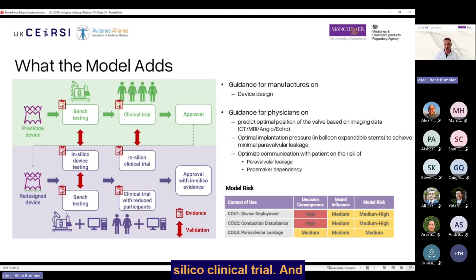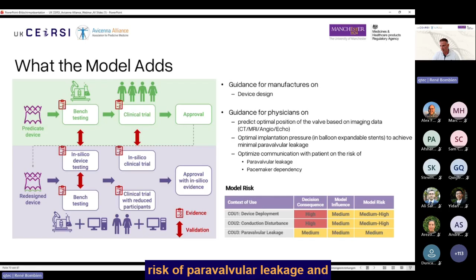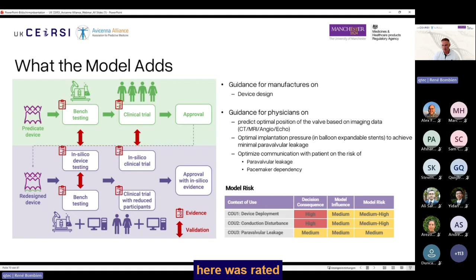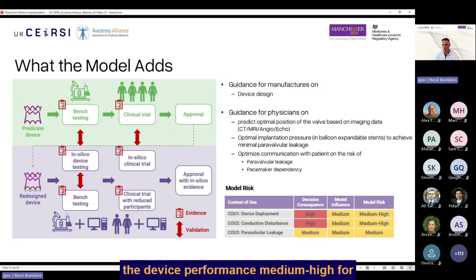What does this add for manufacturers? I mean, definitely add something with regard to the device design, also with regard to iterations. What is for this model with the physicians? Actually a prediction of an optimal position of the valve, optimal implantation pressure, and of course also an optimized communication with the patient, also with regard to the risk of paravalvular leakage and pacemaker dependency. The model risk here was rated medium-high for context of use 1, device deployment, medium-high for conduction disturbance, and for paravalvular leakage, medium.